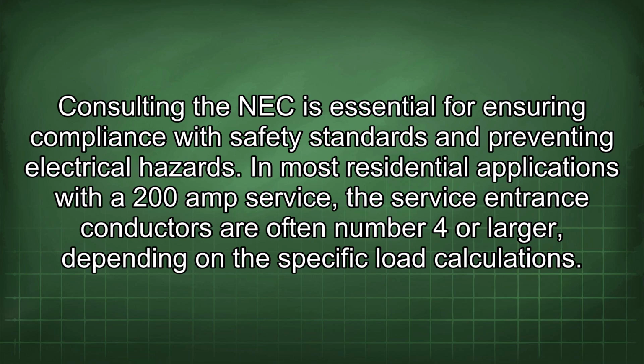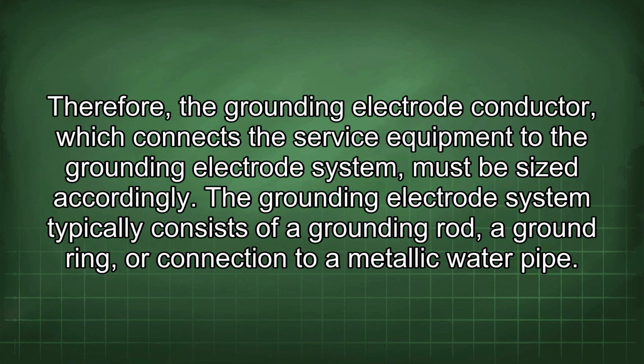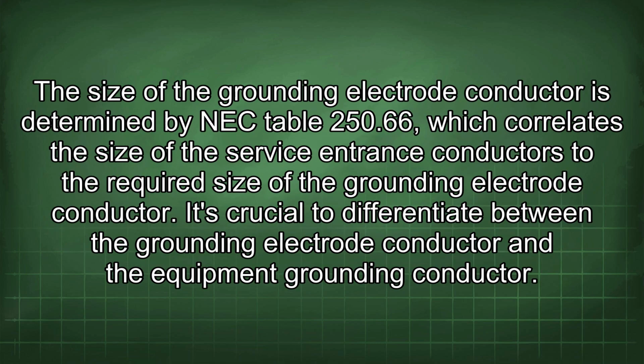In most residential applications with a 200 amp service, the service entrance conductors are often number 4 or larger depending on the specific load calculations. Therefore, the grounding electrode conductor, which connects the service equipment to the grounding electrode system, must be sized accordingly. The grounding electrode system typically consists of a grounding rod, a ground ring, or connection to a metallic water pipe. The size of the grounding electrode conductor is determined by NEC Table 250.66, which correlates the size of the service entrance conductors to the required size of the grounding electrode conductor.